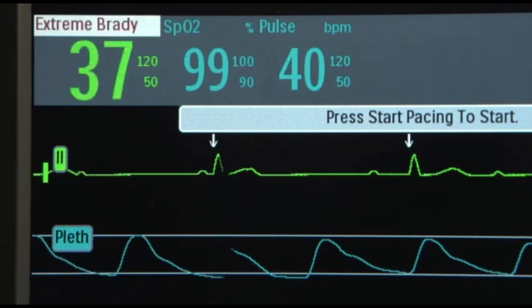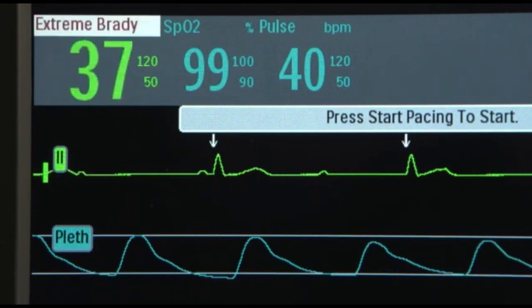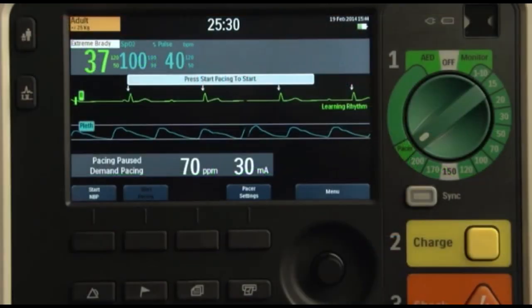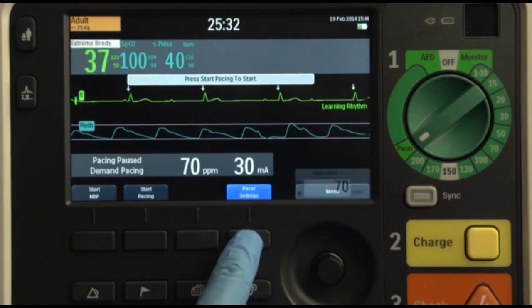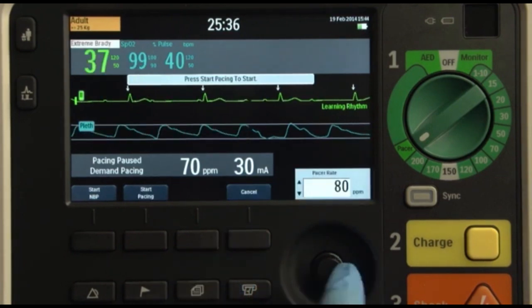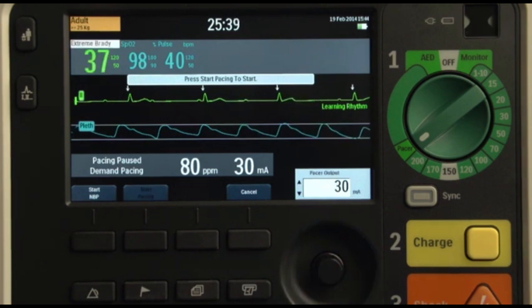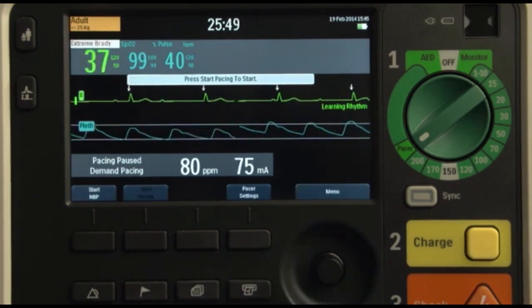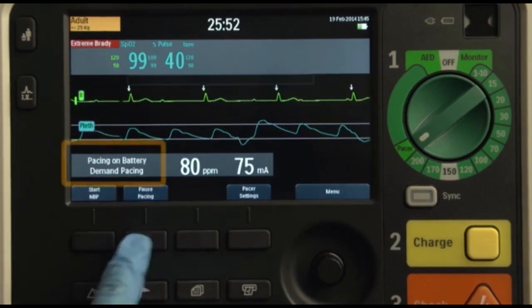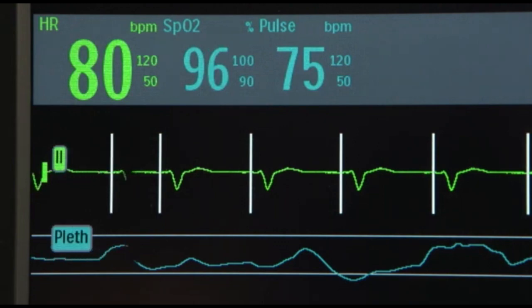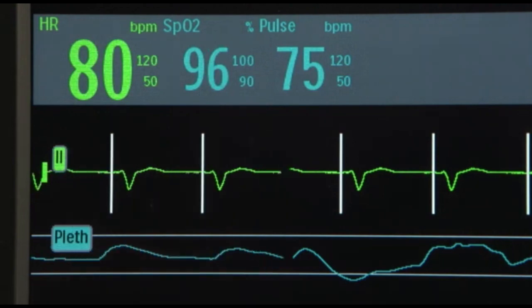In demand mode pacing, the pacer senses the patient's intrinsic heart rate and will pace if the intrinsic signal is lower than the rate programmed by the clinician. For example, if the patient's heart rate becomes slower than the prescribed setting, the pacer will send an electrical stimulus. If the pacer senses that the heart rate is faster than the pacing rate, it inhibits an electrical signal.